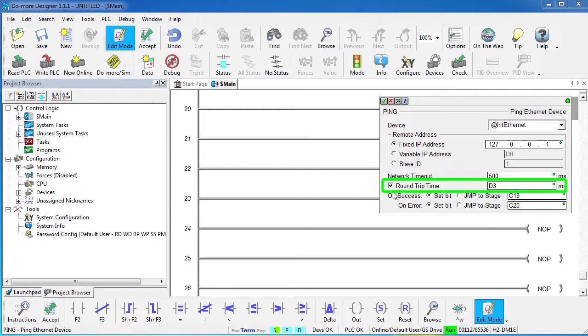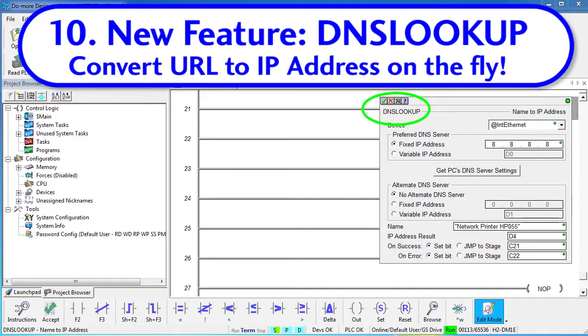The new DNS lookup instruction converts a text URL or computer name to its IP address and puts that in a DWORD register. So now you can use that DWORD register as an input to those instructions that accept IP addresses as variables, such as DEVWRITE, NETTIME, MODBUSREAD, MODBUSWRITE, etc. That means if you have the user provide the name of a device, you can automatically convert it into an IP address that the rest of your instructions can use. That's cool.